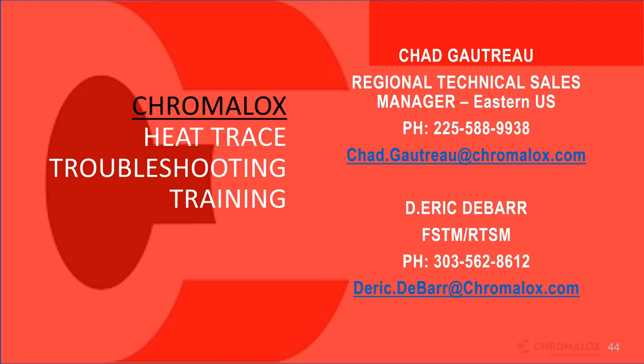You can do the average of the two. You can control off the lowest. So you can do that if you're having an issue maintaining a certain line. But if it's installed properly and it's heat trace and it's insulated properly, you really shouldn't be having that issue. If you're having wind issues, maybe you need to go back and redo your design. Well, and also the sensor mapping too. You can also adjust where you're pulling your sensor from.